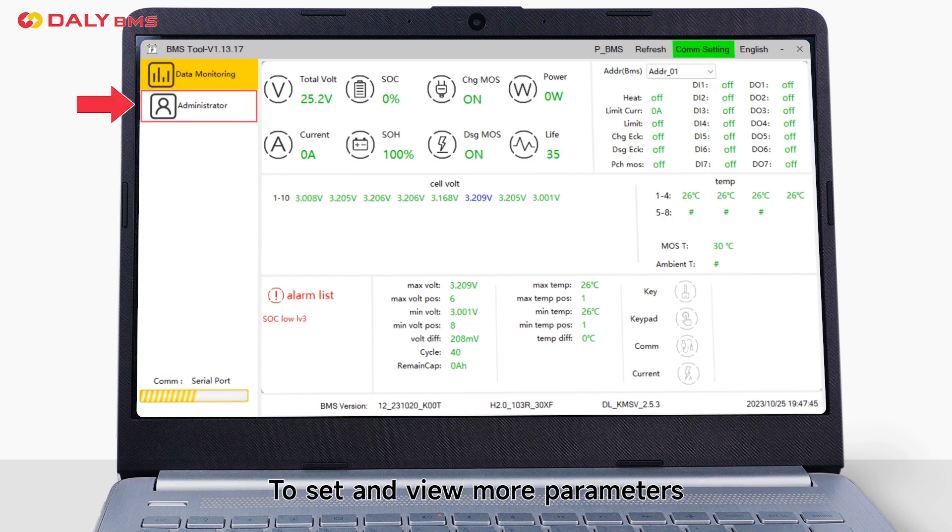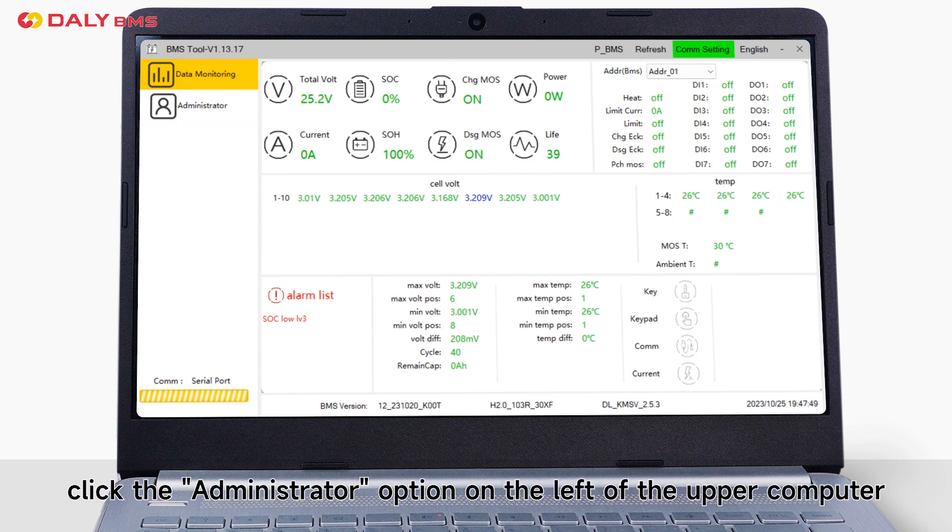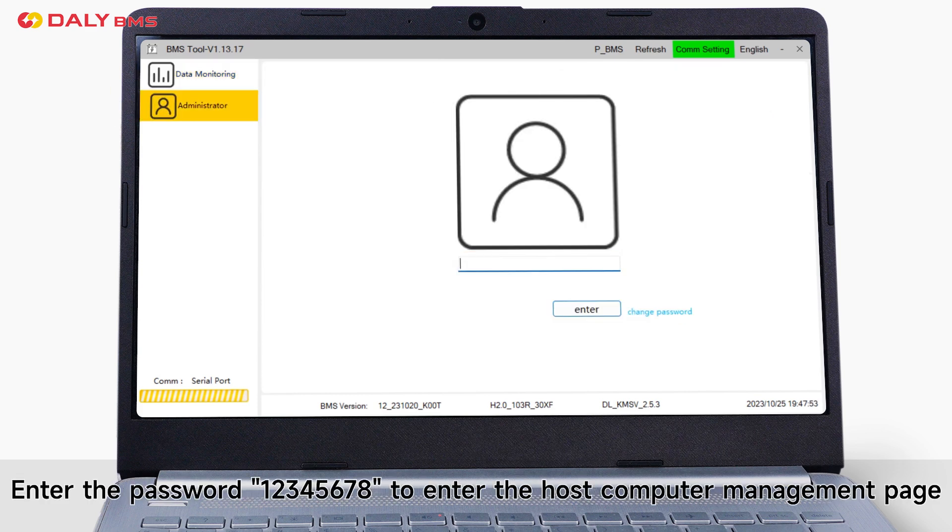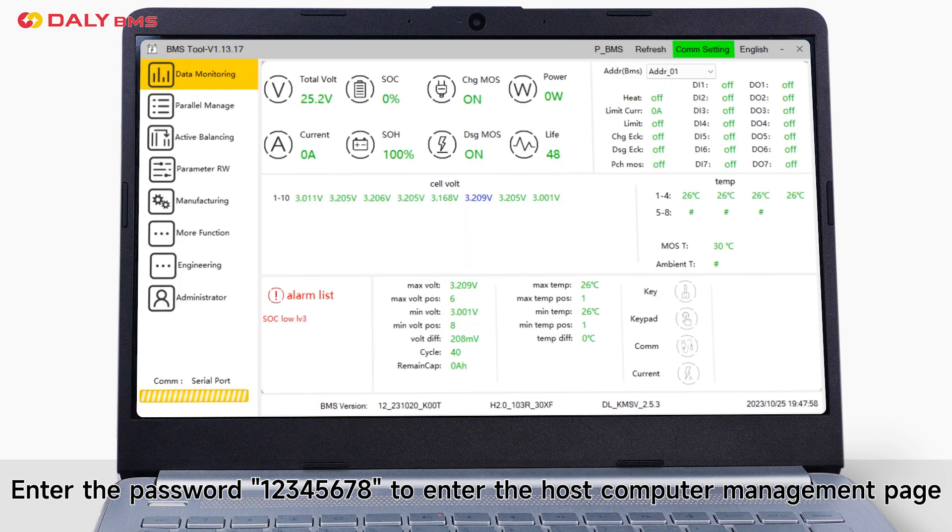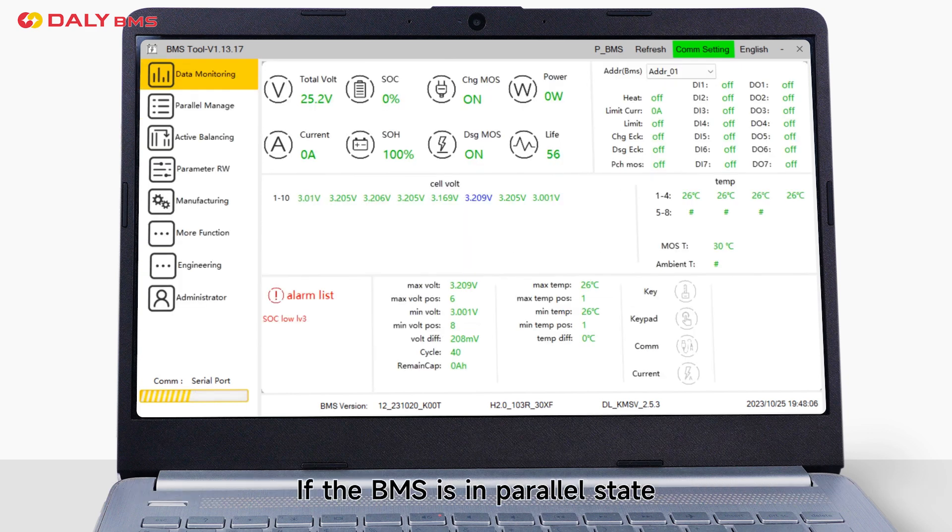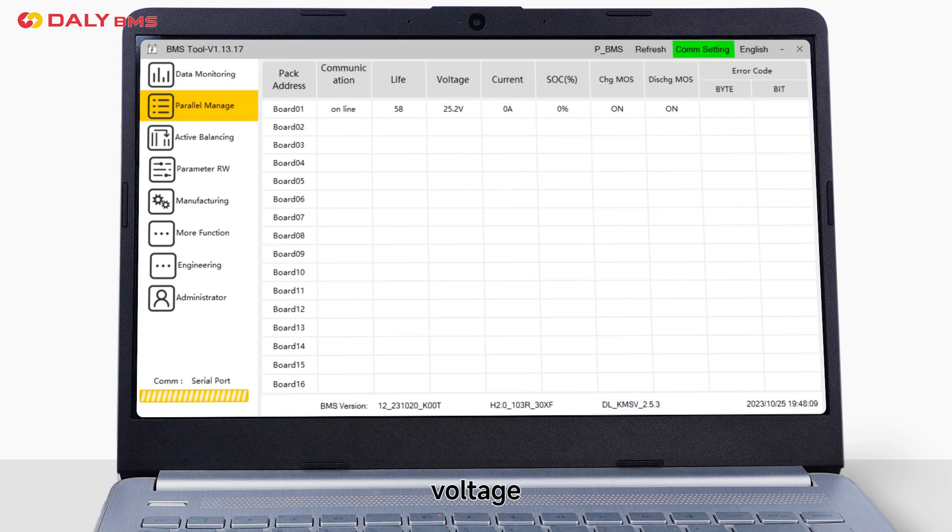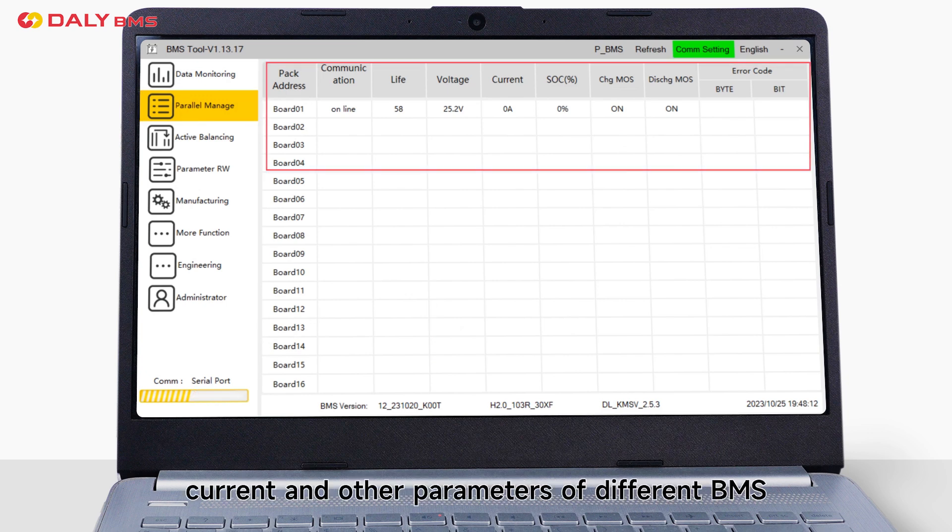To set and view more parameters, click Administrator option on the left of the upper computer. Enter the password "12345678" to enter the host computer management page. If the BMS is in parallel state, click parallel monitoring interface to view voltage, current and other parameters of different BMS.